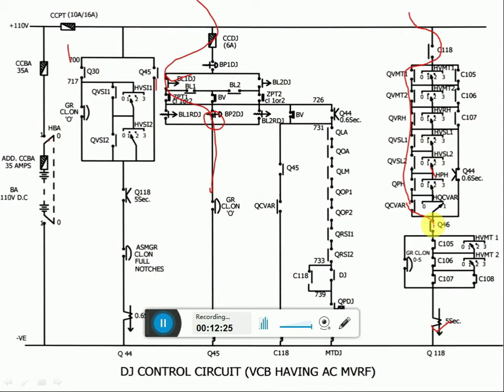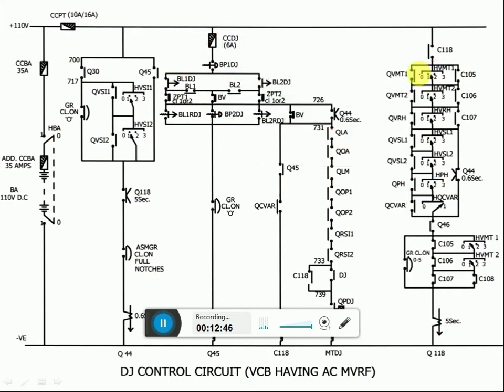If manual operation is also not successful, wedge Q118 in energized condition. If Q118 is wedged in energized condition, we have to follow precautions after wedging of Q118. Ensure C118 is fully open after closing of DJ. So we have to ensure the starting phase was cut off and the C118 contactor was open fully.